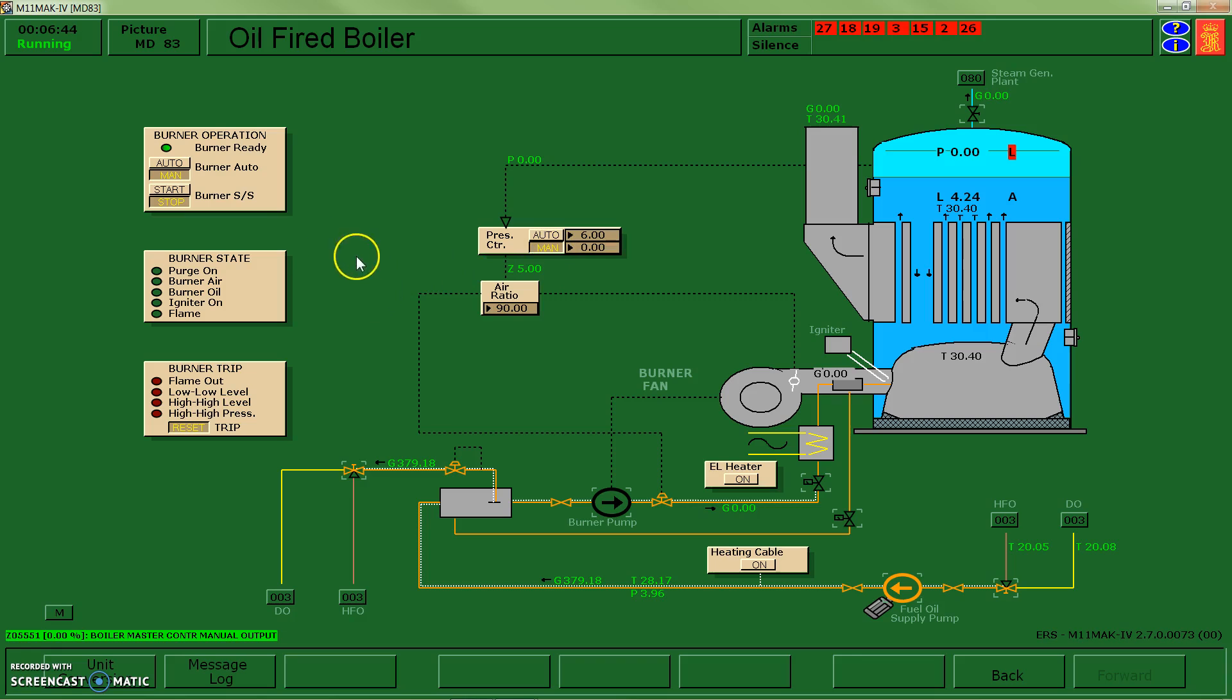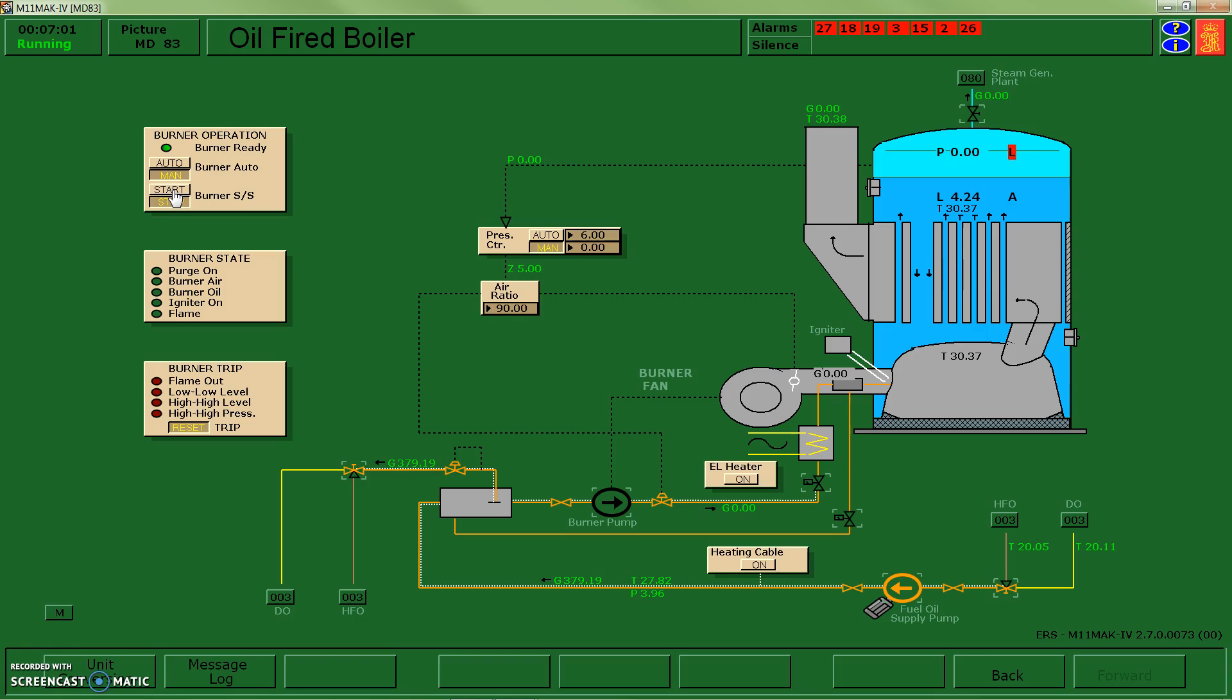And then I'm going to come over and I'm going to tell my burner to start. When I start it, it's going to go through a purge sequence where it blows through air to get rid of any non-combustible gases inside the furnace so we don't have an explosion, followed by the pilot main fuel and air supply coming on, so you'll be able to watch that sequence.